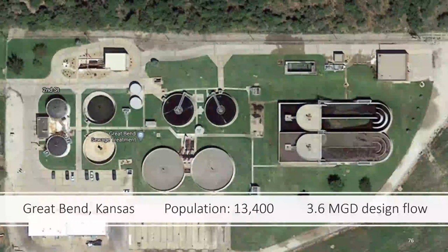So to optimize, there are 2 factors to consider. One is I like to look at hydraulic retention time. So if the plant flow, let's just make it simple, is 1 million gallons a day, and your Schreiber unit tanks are 1,000,000 gallons, then there's 24 hours hydraulic retention time. If there's 2,000,000 gallons a day and 1,000,000 gallons a tank, the retention time is half a day, 12 hours.